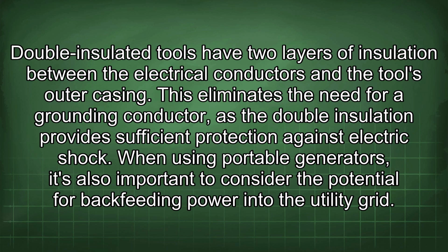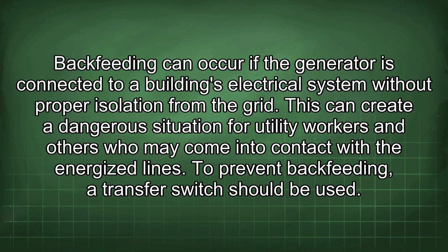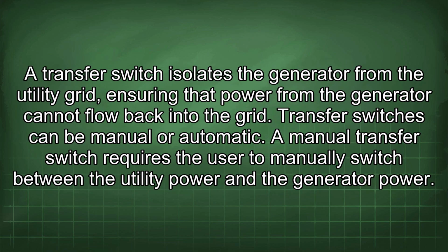When using portable generators, it's also important to consider the potential for backfeeding power into the utility grid. Backfeeding can occur if the generator is connected to a building's electrical system without proper isolation from the grid. This can create a dangerous situation for utility workers and others who may come into contact with the energized lines. To prevent backfeeding, a transfer switch should be used. A transfer switch isolates the generator from the utility grid, ensuring that power from the generator cannot flow back into the grid. Transfer switches can be manual or automatic.